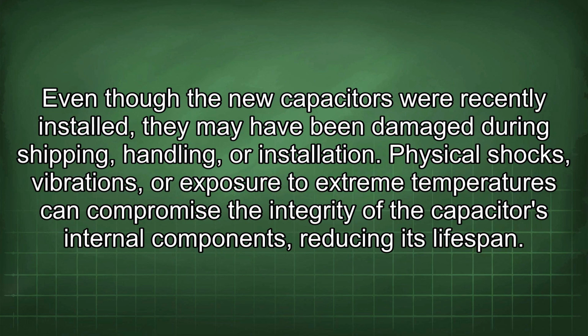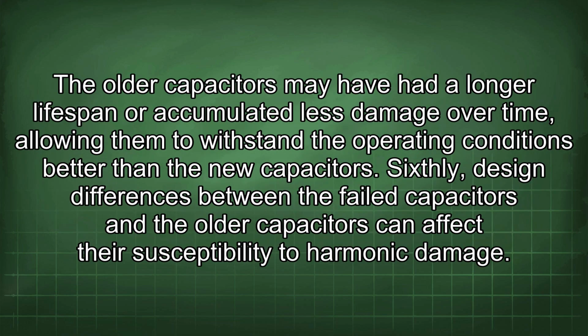Even though the new capacitors were recently installed, they may have been damaged during shipping, handling, or installation. Physical shocks, vibrations, or exposure to extreme temperatures can compromise the integrity of the capacitor's internal components, reducing its lifespan. The older capacitors may have had a longer lifespan or accumulated less damage over time, allowing them to withstand the operating conditions better than the new capacitors.